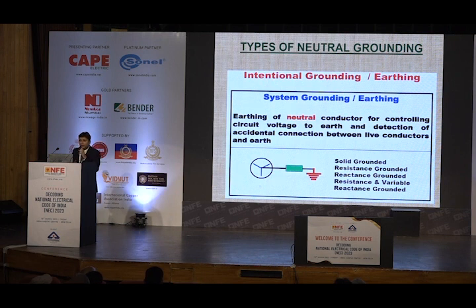When I say effectively grounded or earthed systems, that is basically denoted by a factor called the coefficient of grounding and earth fault factor. The coefficient of grounding and earth fault factor tell you the characteristics of the grounding system you are using. That tells you, at the time of a single phase to ground fault, what is going to happen as a TOV for the healthy phases in the system.